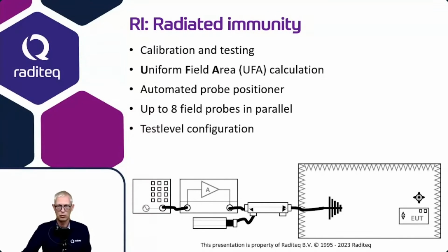And it can also include limitations, like I would like not to go higher than 100 watts out of the amplifier. But limitations or requirements with currents and voltage levels are also available. So the test level configuration allows the end user to specifically state how the regulation of the power should be performed, what the limitations are of the maximum power being generated, and how it should be regulating to that.